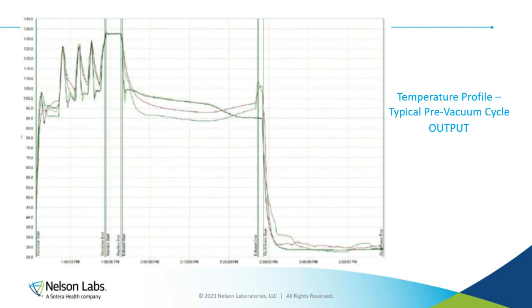This is an example of a pre-vacuum full cycle. You can see the preconditioning pulses, the exposure phase, and the drying phase before venting and coming out of the chamber.